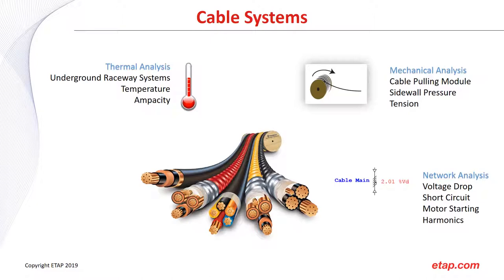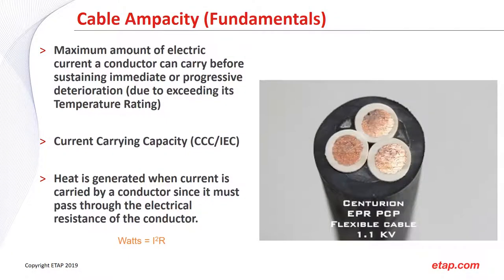Now let's cover the fundamentals. Cable ampacity is essentially the maximum amount of electrical current a conductor can carry before sustaining immediate or progressive breakdown, due to exceeding its temperature rating. Whenever you order or purchase a cable, there is a TC rating — a maximum allowed temperature — specifying how much current that cable can carry. We'll go over some sample data sheets later so we can see where that information is found.